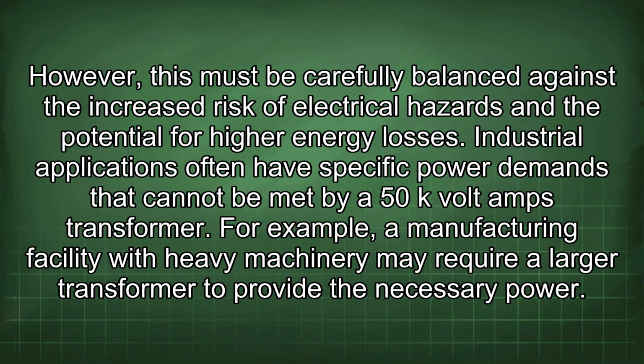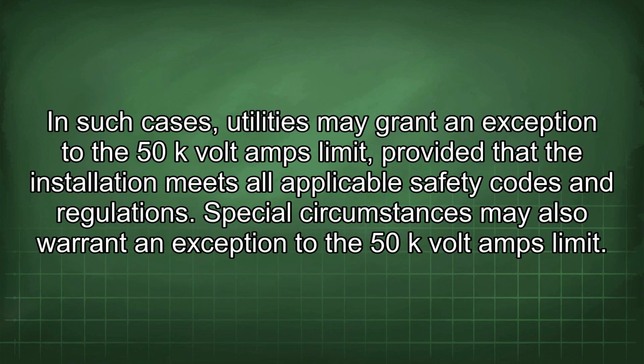Industrial applications often have specific power demands that cannot be met by a 50 kVA transformer. For example, a manufacturing facility with heavy machinery may require a larger transformer to provide the necessary power. In such cases, utilities may grant an exception to the 50 kVA limit, provided that the installation meets all applicable safety codes and regulations. Special circumstances may also warrant an exception to the 50 kVA limit.